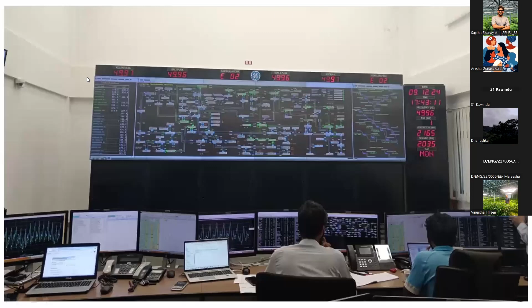At the top you can see the total generation. Actually the load curve you saw a few slides before is plotted using this total generation. It is not actually the demand - there is no way to measure the demand directly. So what they do is measure the generation, since there are only a few power plants, so easily through SCADA they can collect those values, add them up, and get the total value. Then they plot this total generation and consider it as the demand curve.